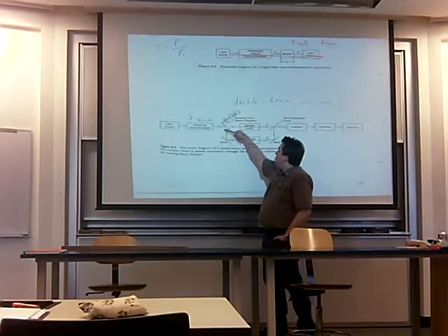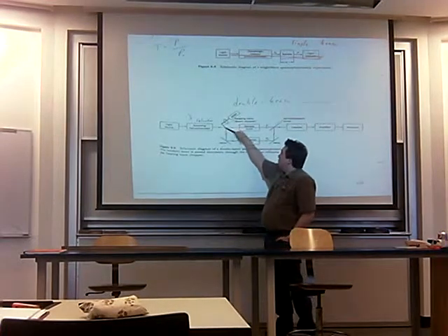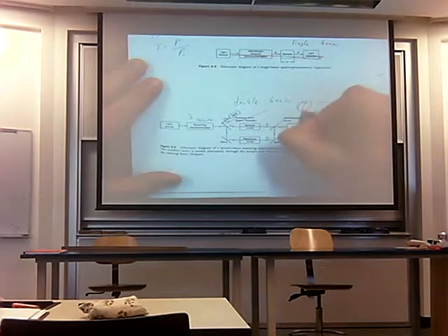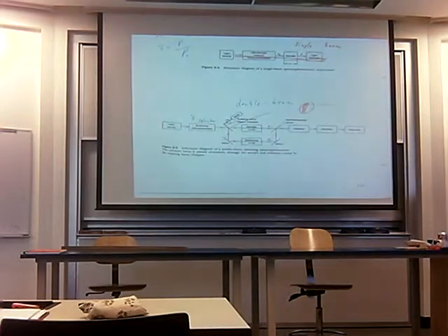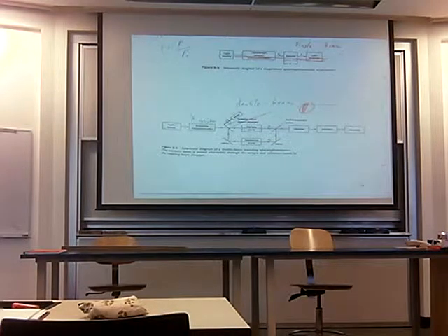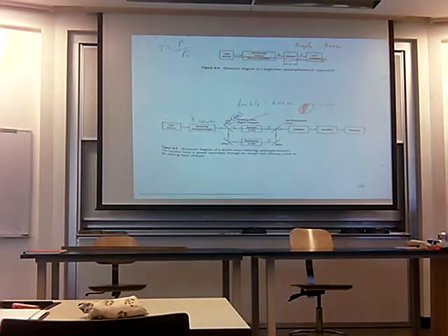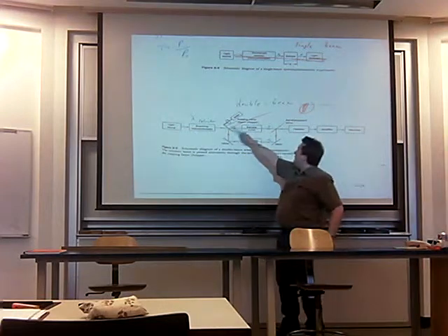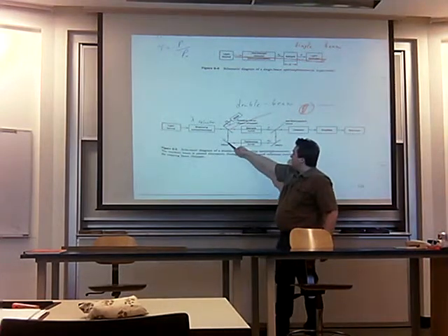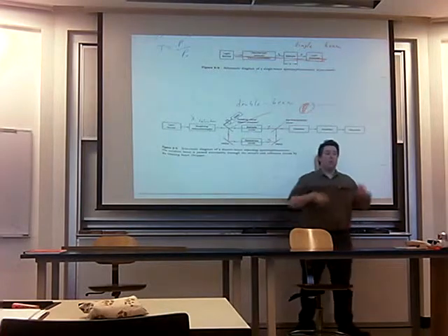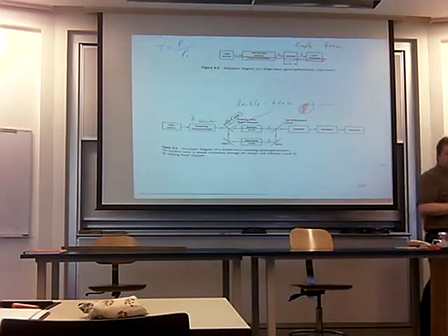This one uses a rotating mirror. If we're looking at the side of this, and if we look at this straight on, it would be a circle where half of it would be a mirror and half of it would be open. And as this mirror is on a motor and spinning, when the mirror side is in line, the light is reflected down through a reference cuvette where you can put in your blank material.